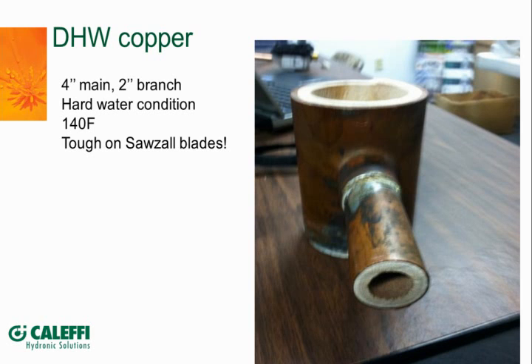This might be a great time to interject that the glycol manufacturers will state rather definitively that when you start working with glycol concentrations less than 25%, you dramatically increase the possibility of bacterial contamination. So you can get slime growing and so forth in your glycols when you're working with concentrations less than 25%. We ran our tests at 20% solutions because we were mixing with clean water for the most part. But if there's any situation where a makeup water might come from the city's supply, heaven forbid that it would, but if it did come from an outside supply, it's best to keep that glycol concentration at 25% or just a little bit higher to try and forego any possibility of bacterial growth within that glycol solution.